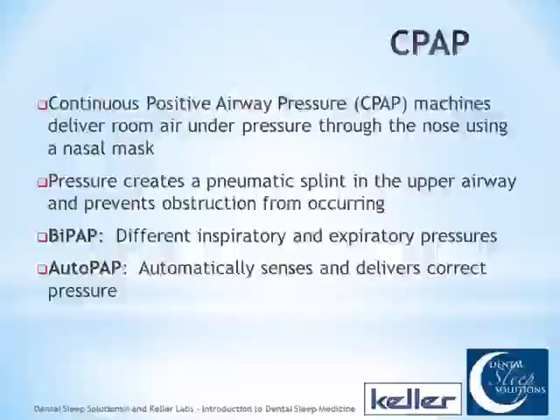That's good, Guy. And I want to add, too, that when we ask patients, what's your CPAP set on? Most of them will know. They may say it's at 12, and that number is the centimeters of water that the machine is actually adjusted to. So an AutoPAP will adjust that based on some of those other parameters. A BiPAP will have two settings. It will be 12/8, for example. So the inspiratory would be 12, the expiratory would be 8.